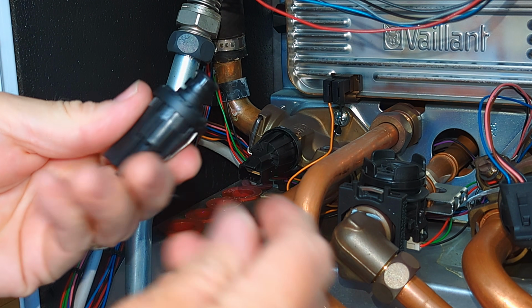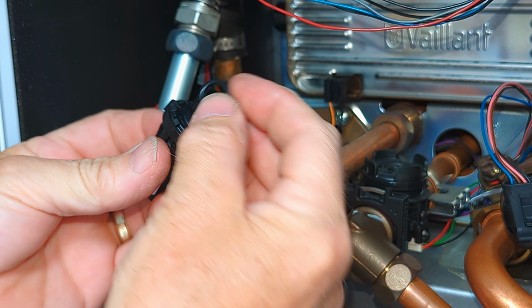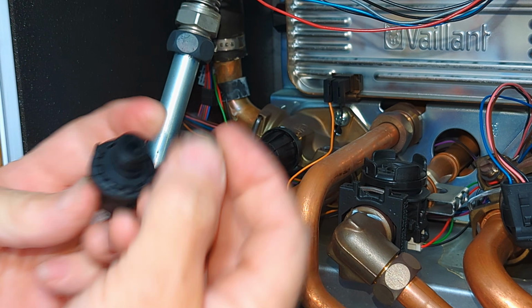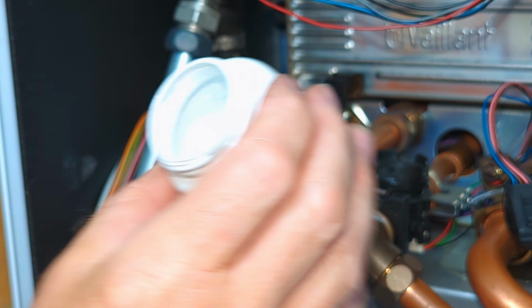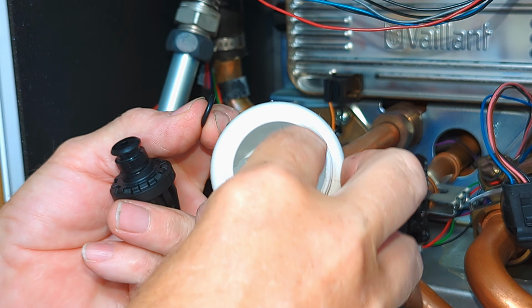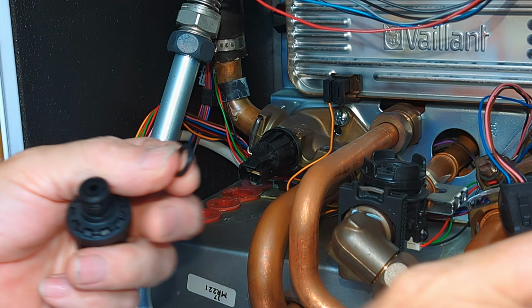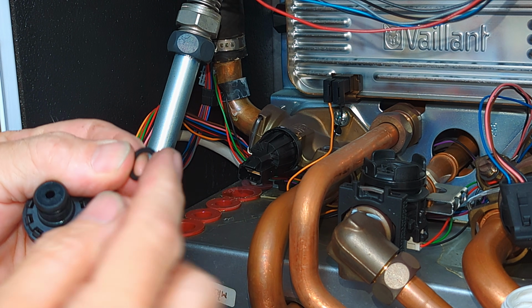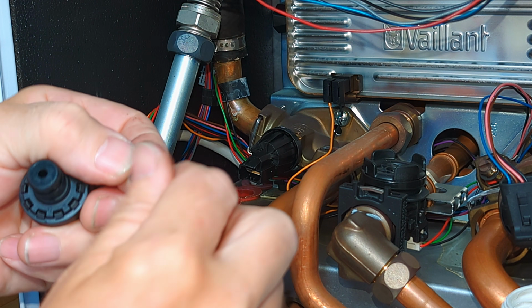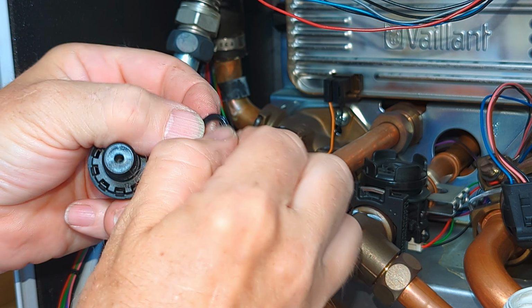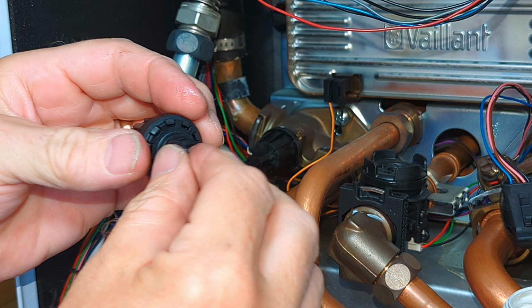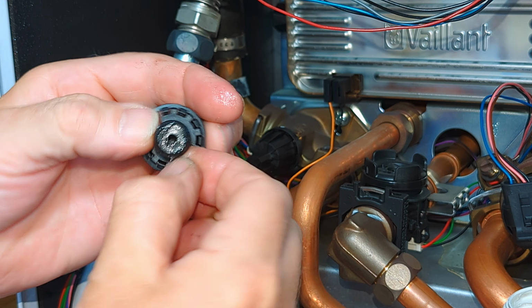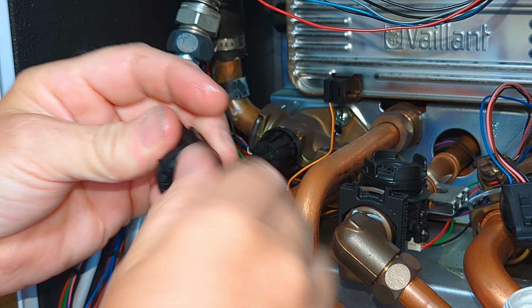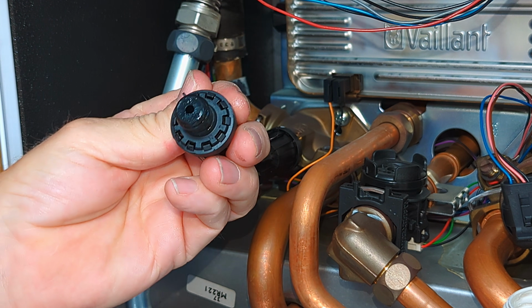So here is my new pressure sensor, and here's the O-ring which goes onto the pressure sensor to seal it. As usual, I'm going to use some silicone grease to grease up the O-ring so I get a good seal, and then I'll just wipe that around the O-ring, and then I slip the O-ring onto the pressure sensor so that I get a really good seal. And there we are, that's that done, and now that is prepared and ready to go straight in the hole.